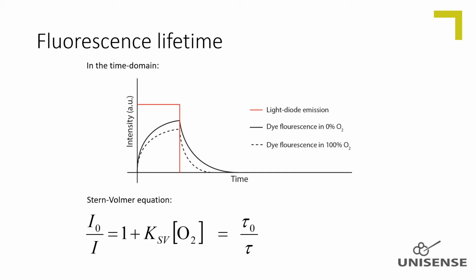The intensity still has a role to play. The more intense the back-emitted fluorescence light is, the more precise the tau response can be measured. So although bleaching does not affect the actual tau response, the calculation of it gets statistically inaccurate with a decreasing intensity, and the resolution of measurements will therefore gradually decrease with the bleaching.